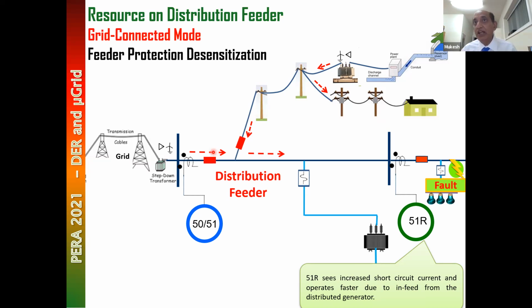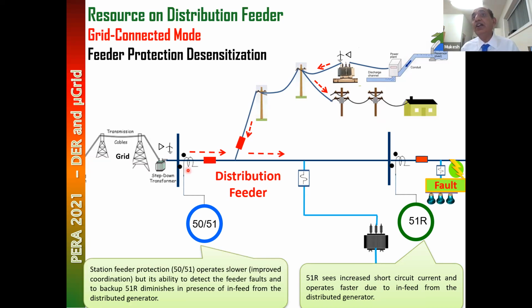What it means is that this protection sees less current and will operate slower. Good. We are even happy that this protection operates faster and this protection operates slightly slower. Our protection margin is improved, our coordination is becoming better. Why should we worry? We should worry in one case. Because this protection is seeing less current, what if this protection fails? The inverse time protection is providing a backup. This protection is providing a backup to this protection. If this fails, this has to operate. Now the fault current reduces. If it reduces to a point, and that happens if this source is strong and this utility source is weak, that happens in my system.